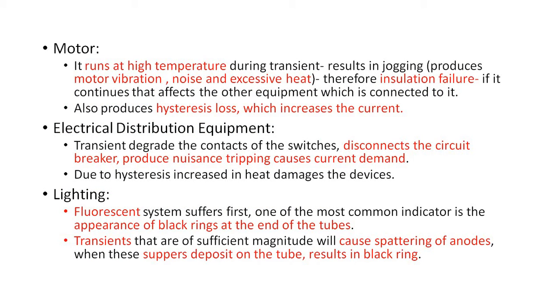So next, the motor. It runs at a high temperature during a transient, resulting in jogging, and produces motor vibration, noise and excessive heat. Therefore, insulation failure occurs if it continues, affecting the other equipment connected to it. It also produces hysteresis losses, which increase the current. Electrical distribution equipment: a transient degrades the contact of the switches, disconnects the circuit breaker, produces nuisance tripping, and causes current demand. Due to hysteresis, the increase in heat damages the device.